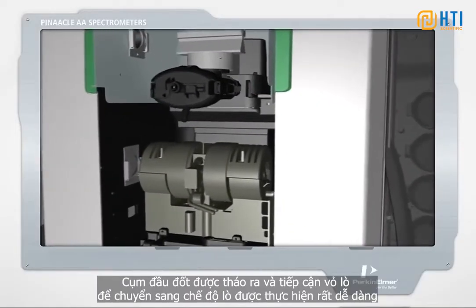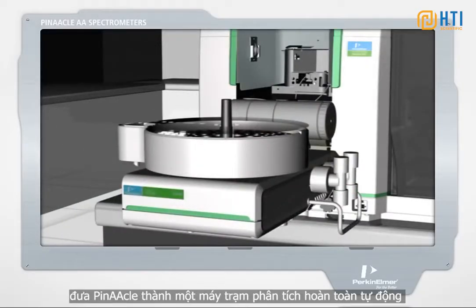Switching to furnace mode is as easy as removing the burner assembly to gain access to the furnace housing. The system's AS900 auto-sampler quickly and easily rotates into place, turning PinAAcle into a fully automated analytical workstation.